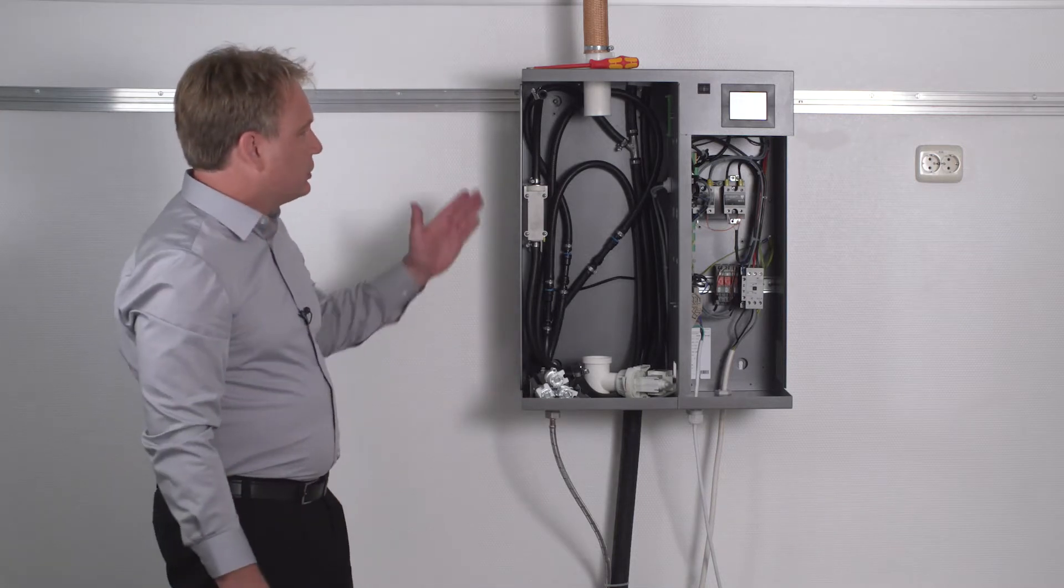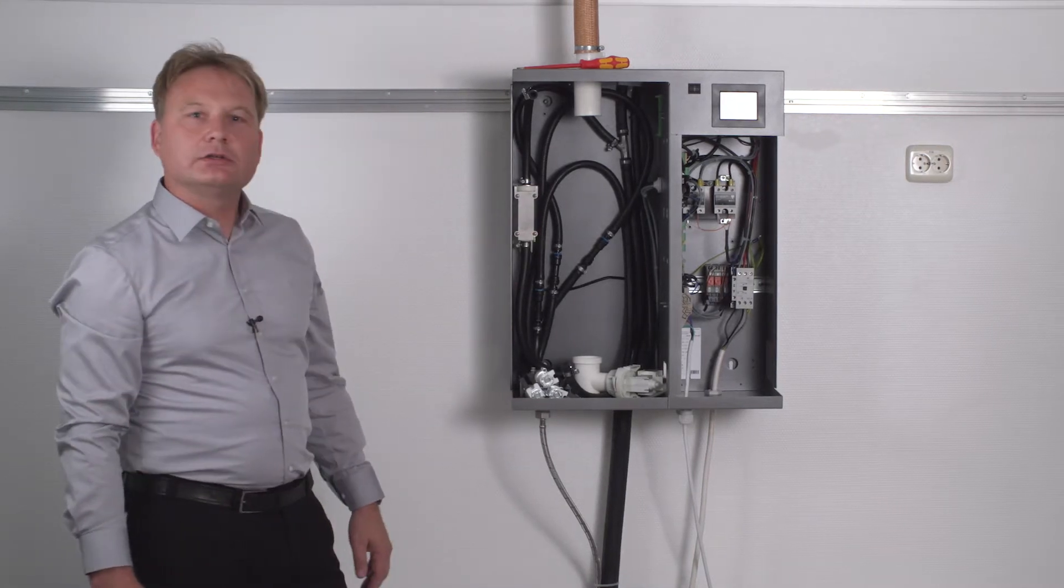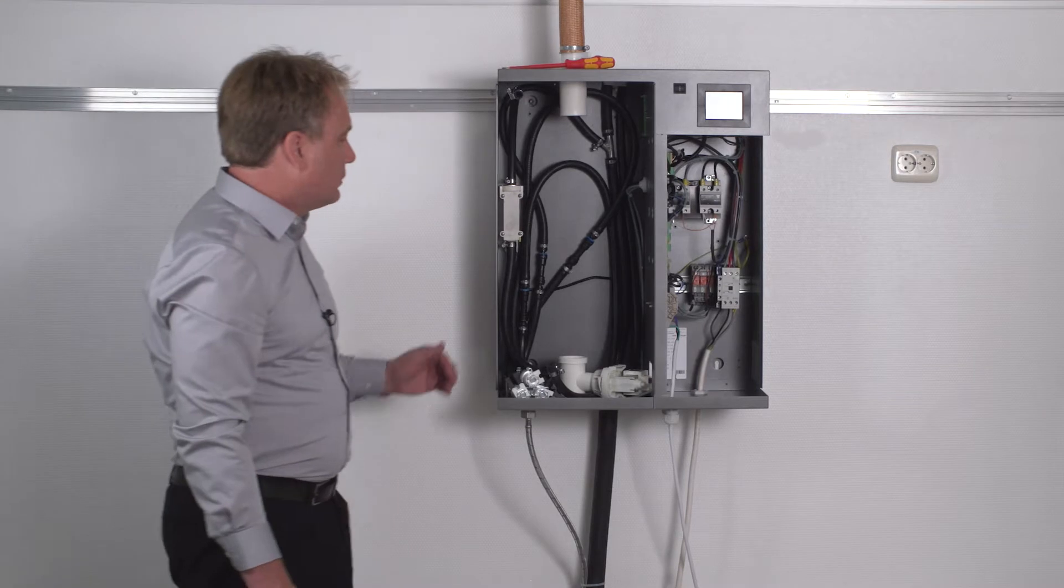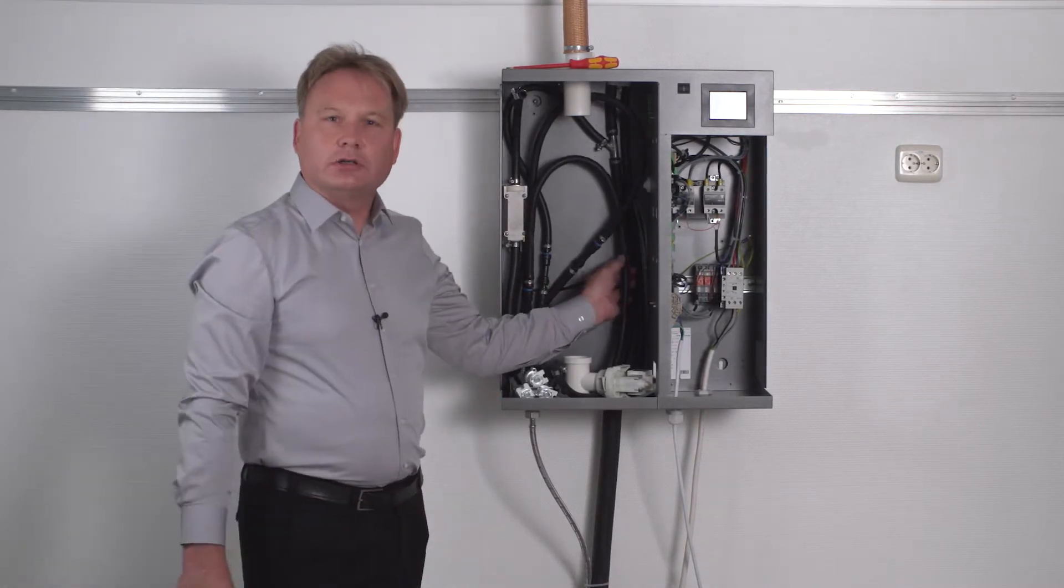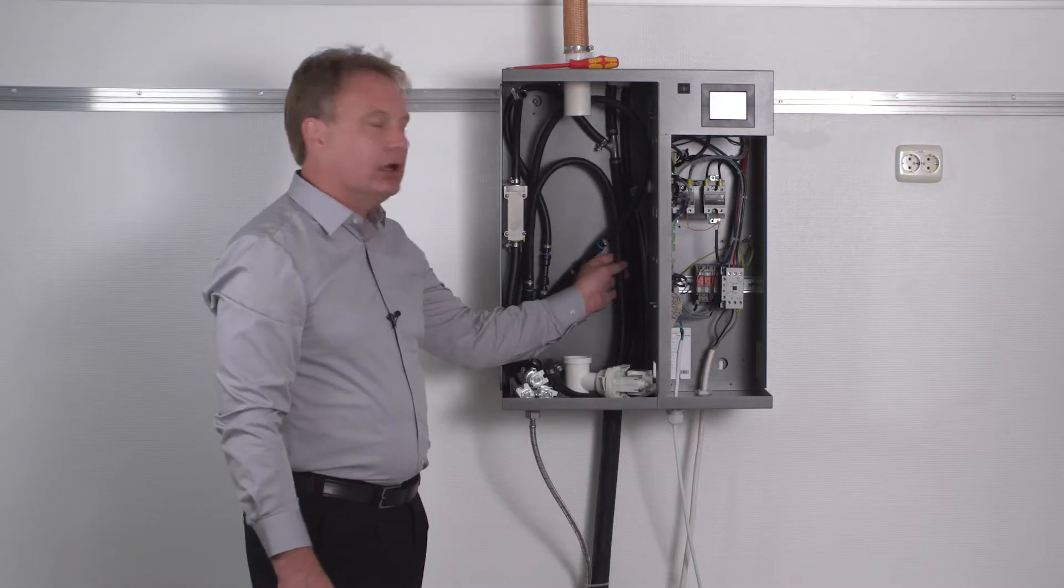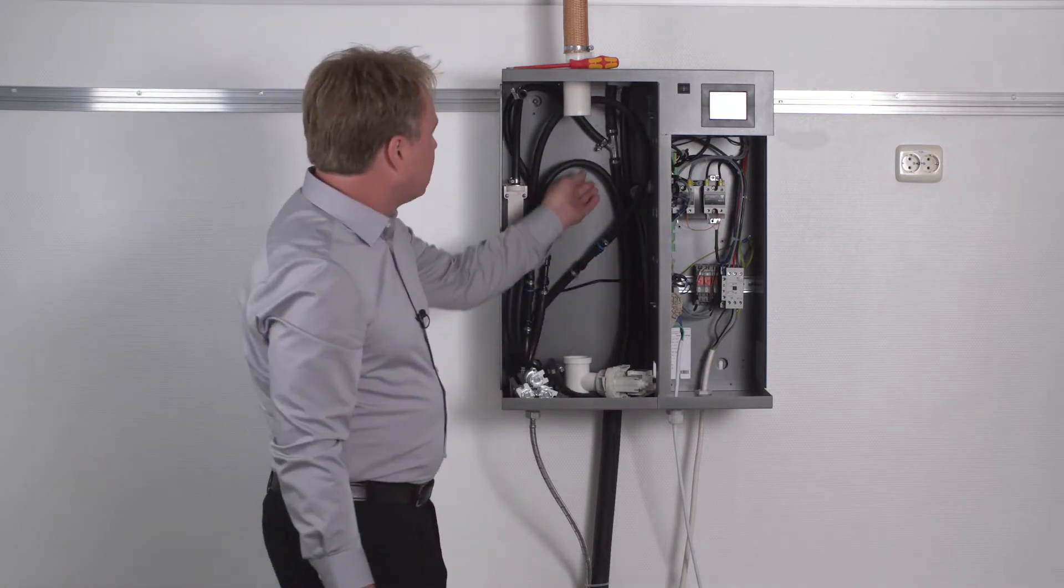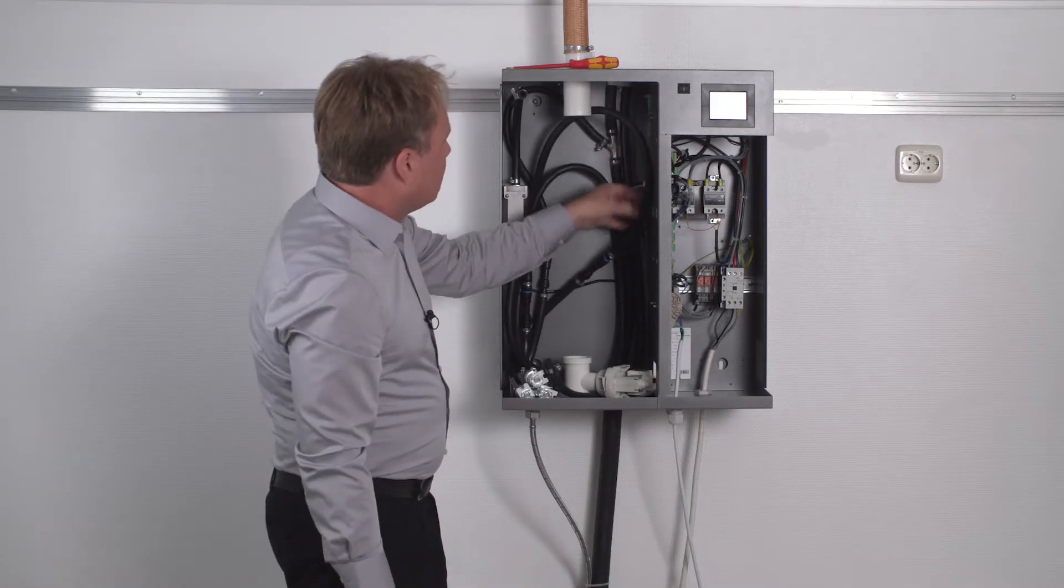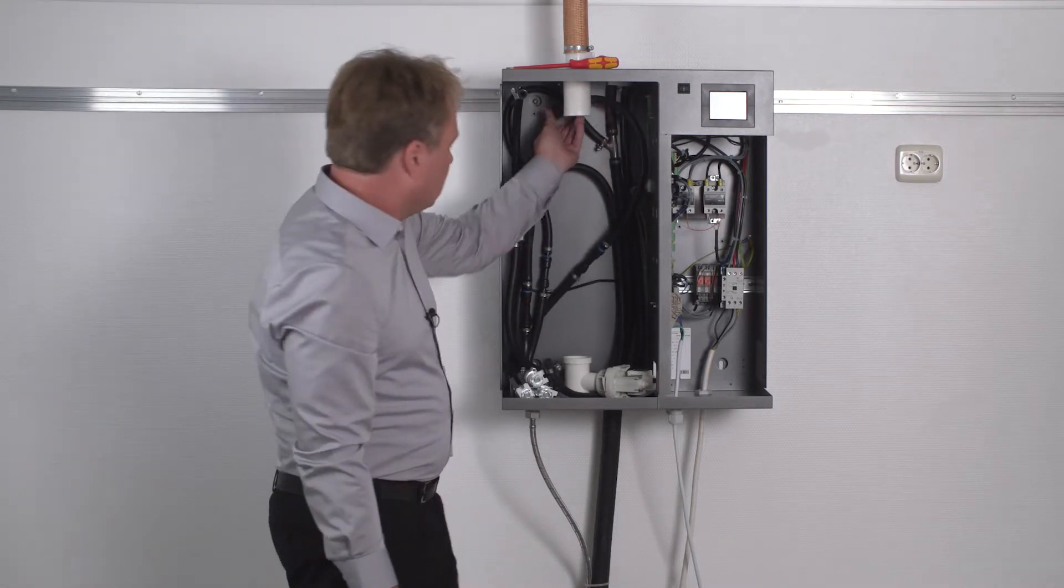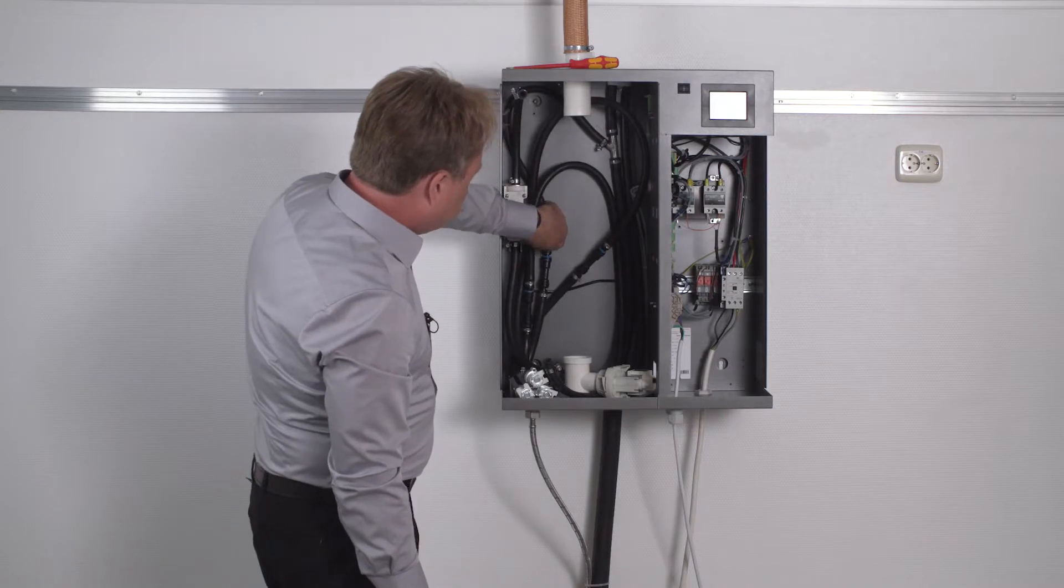Now that the cylinder has been serviced, I take a look at all the hoses in the steam compartment. I have to make sure that the hoses are still flexible. If they have hardened, you can check by kneading them a bit. Notice if they have become brittle and porous. That is not the case in this case.